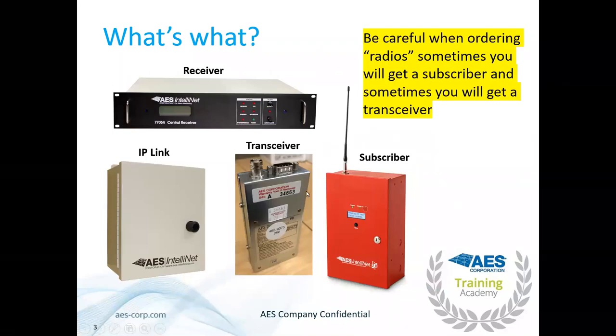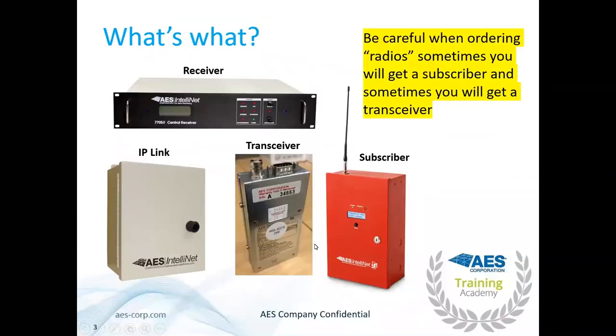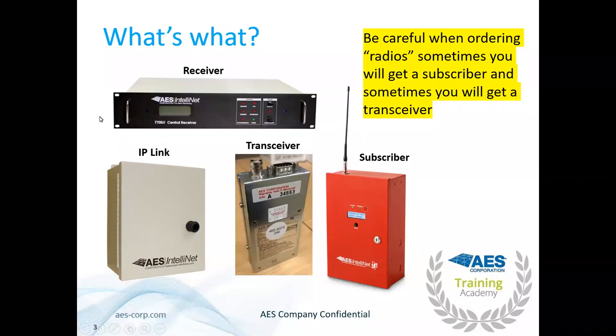Here's a brief highlight of the AES radio technology. We have our subscriber here — this is what most people call the radio. Signals will hop between subscriber and subscriber until they get back to the IP link. What the IP link does is change the radio data into IP data and send it along to the receiver, which is located at the dispatch center and monitored by the alarm automation software.